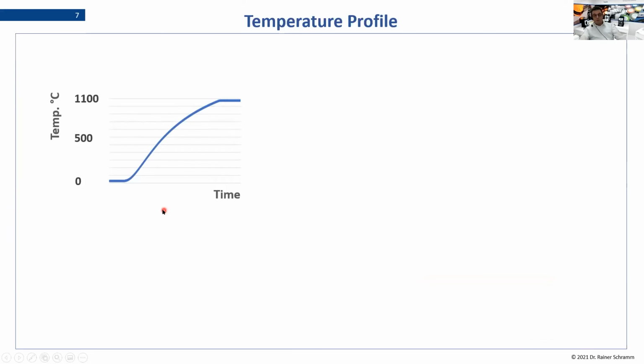Of course, when you have such a furnace, the important point is also how long it needs to heat up. So when you come in the morning, how long do you need? In this case, our furnace needs about an hour. And we have integrated a time-based heating. That means you can program energy saving times. Overnight you can switch it off, and when you come in the morning, it's already at temperature. So when you program it to be ready 1 hour before you start work, it will be heated up.